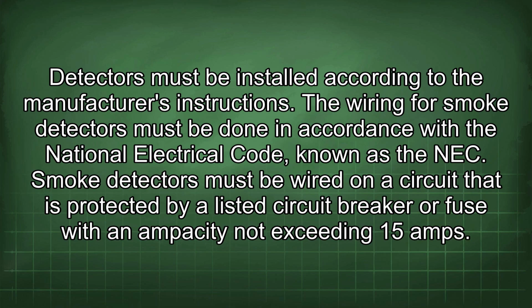Detectors must be installed according to the manufacturer's instructions. The wiring for smoke detectors must be done in accordance with the National Electrical Code, known as the NEC. Smoke detectors must be wired on a circuit that is protected by a listed circuit breaker or fuse with an ampacity not exceeding 15 amps.